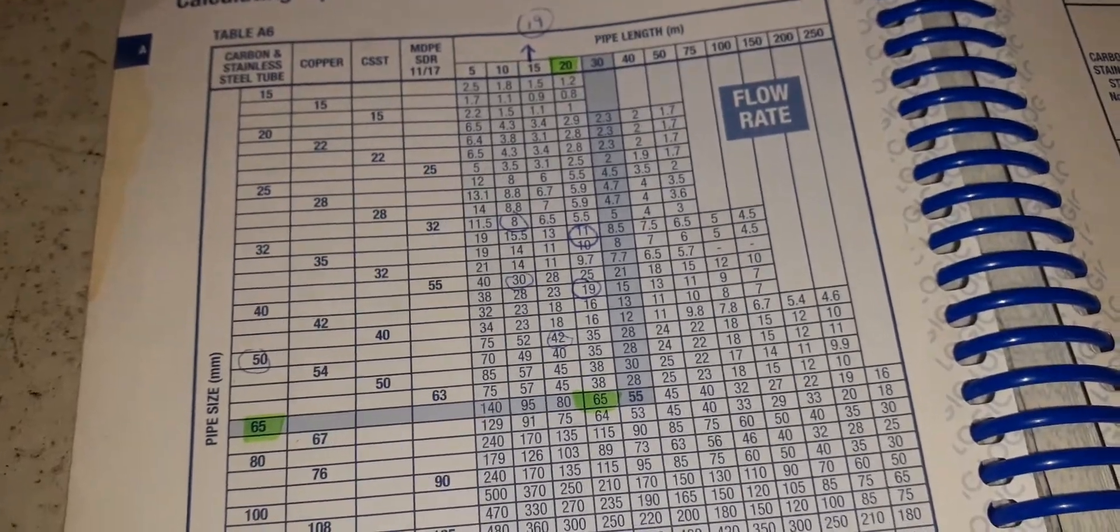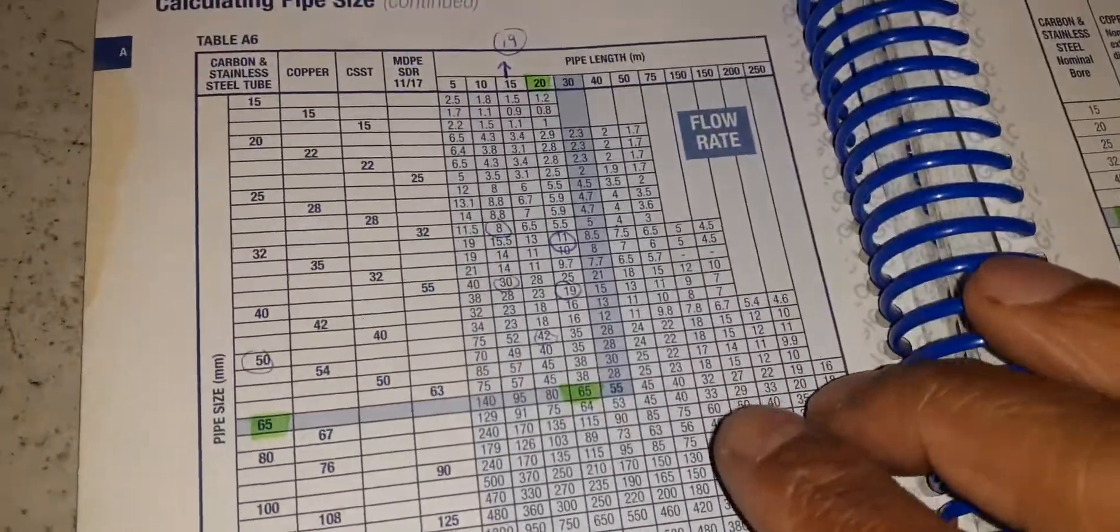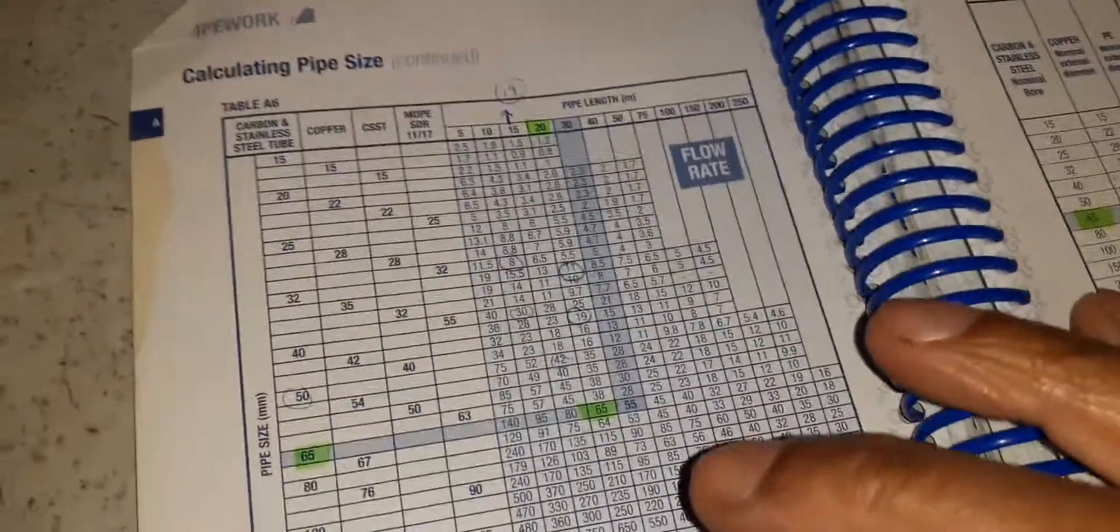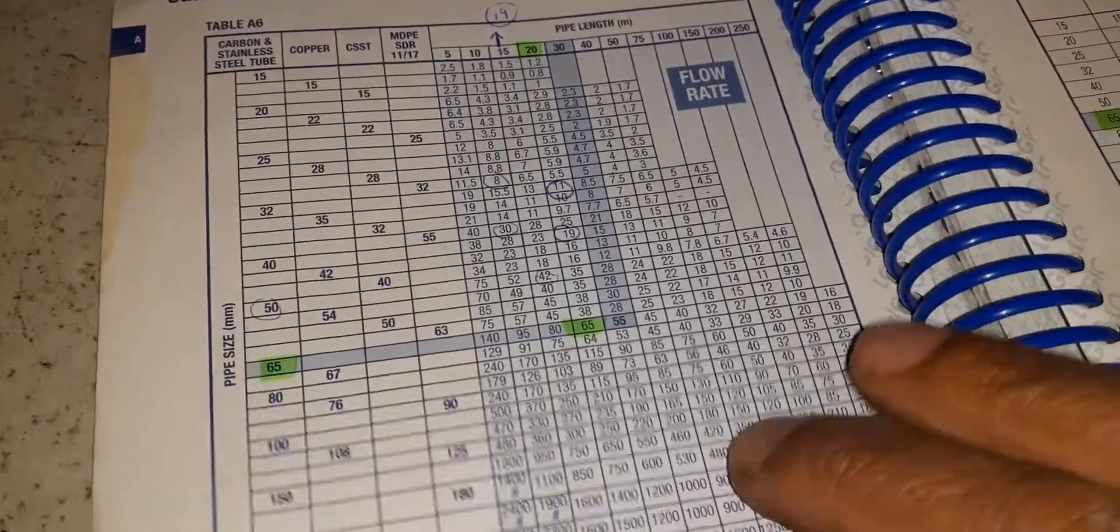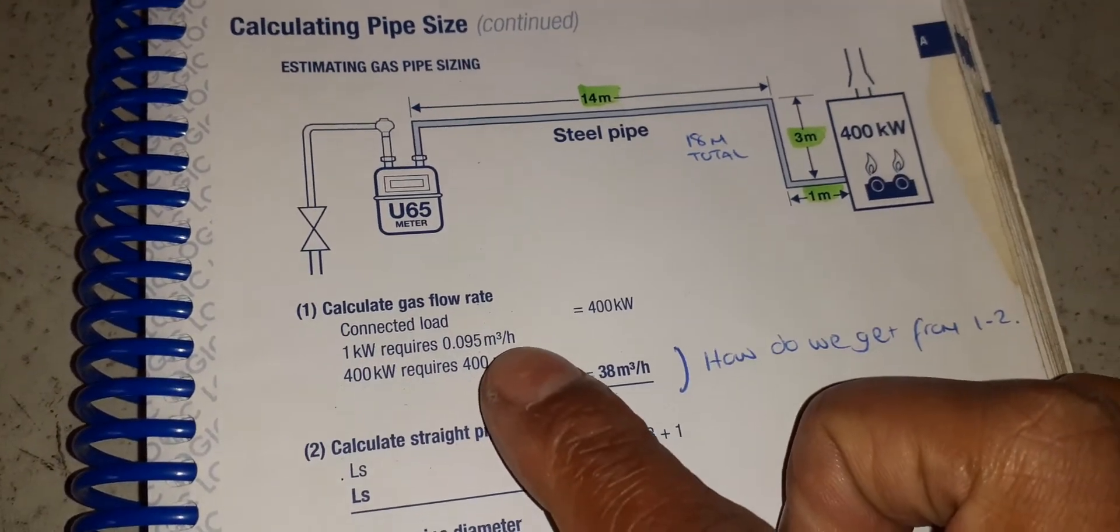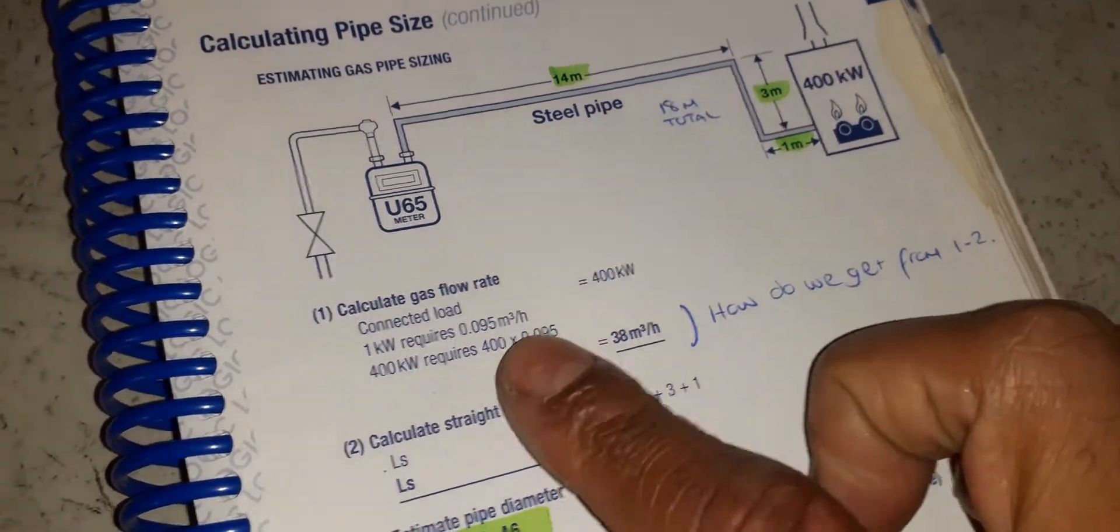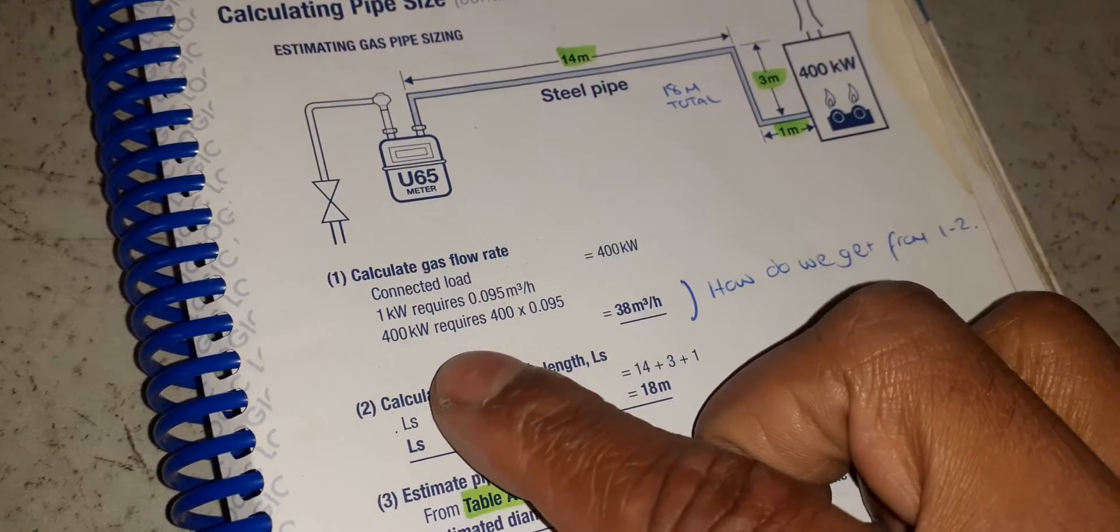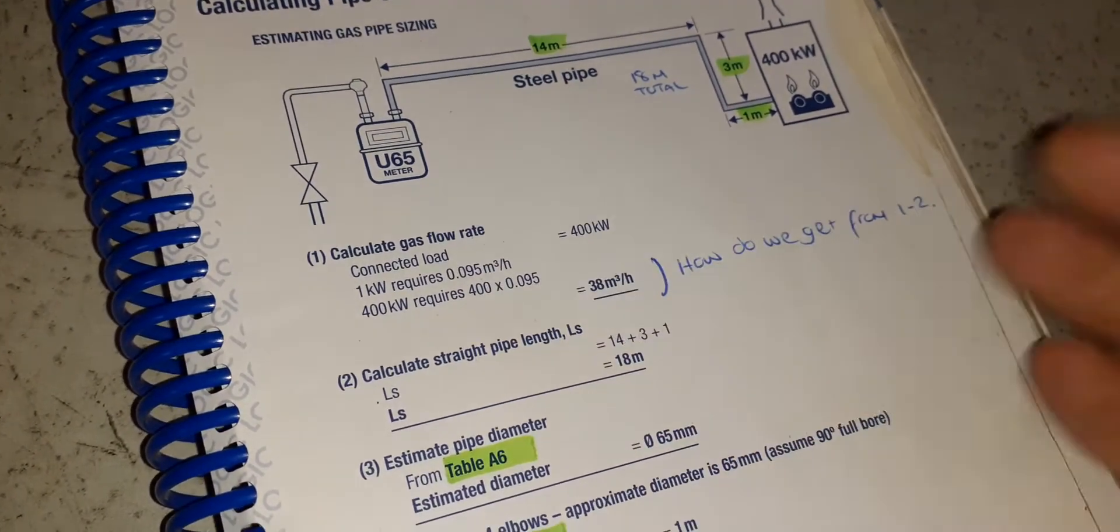Right, I have such and such. You do your calculation whether it's a 200 kilowatt, 300 kilowatt boiler, and then you times it by the recommended amount for each kilowatt, which is 0.095 meters cubed an hour for every kilowatt.